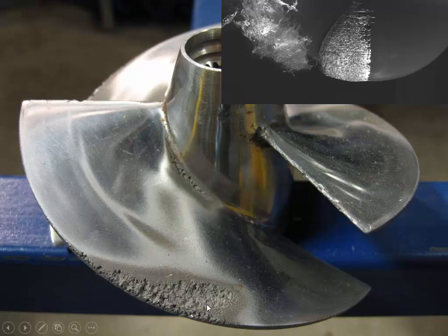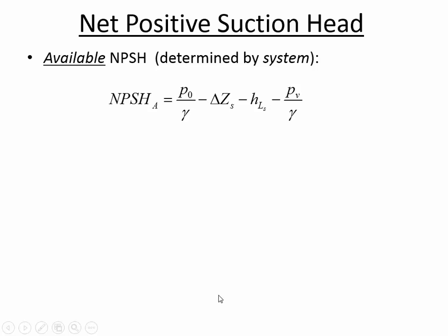Here's an impeller that was damaged by cavitation. You can see that there's pitting on the outside edge of the blade. And this is where the pressure is going to be most negative, on the outside edge of the blade. So avoiding cavitation can be ensured if you do these calculations that have to do with net positive suction head. And the way it works is you start with atmospheric pressure, P naught. And any one of these three things can get you closer and closer to danger.